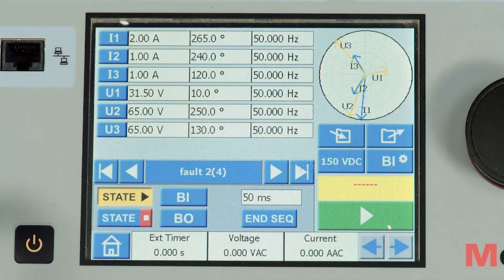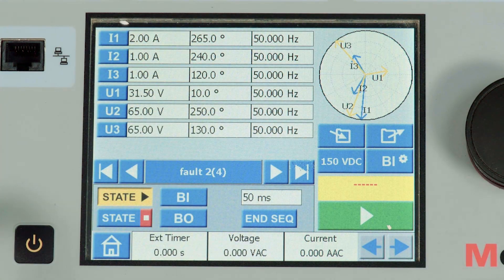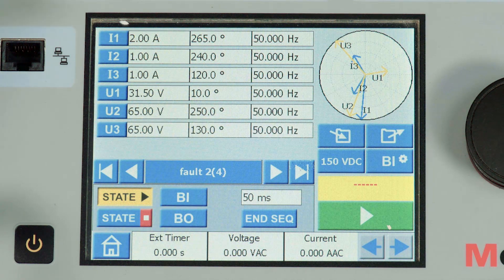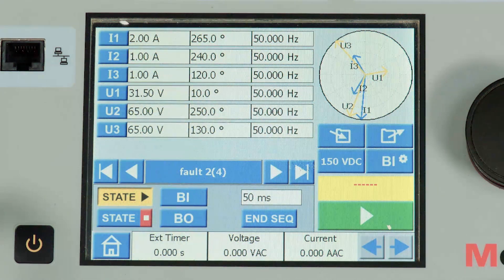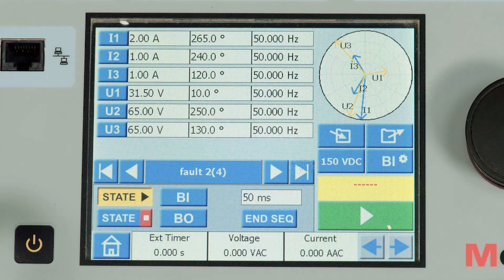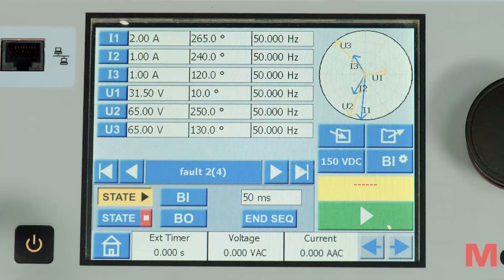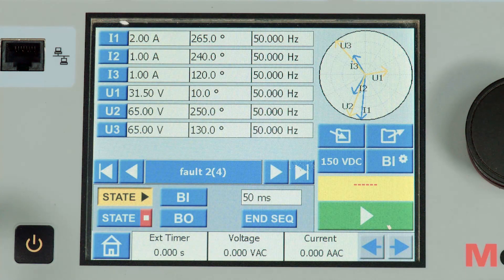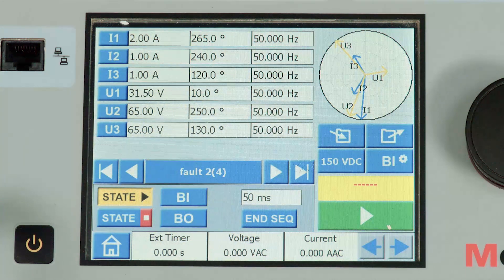In the second state we have renamed it as a fault state. I am creating an R phase to ground fault where 2 amps the voltage and R phase is dipped to 31.5 volts. This state persisted for 50 milliseconds.